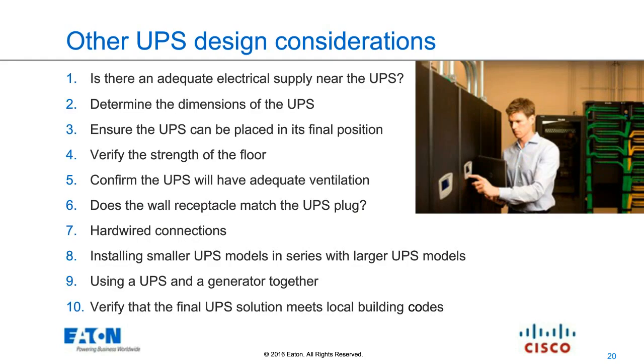So to unpack a few of those things a little more: the electrical supply coming into the space. Time and time again, my team sees customers calling in that just don't have the necessary utility coming into the space where they're trying to put this V-block or any other CI rack, or maybe they're trying to put together their own, and they just don't have enough power coming in. So that's a good conversation to have up front. Eaton can help make sure you're asking the right questions and getting connected to the right contractor to bring that supply to the UPS.